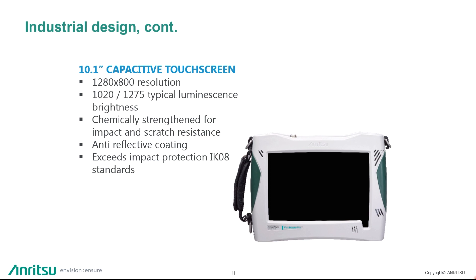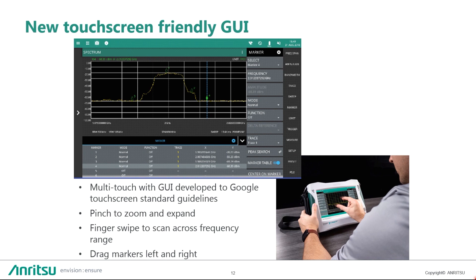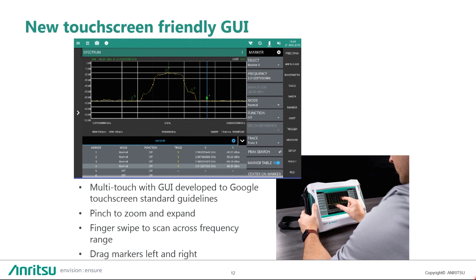We also created a new touchscreen with a friendly user interface. This is multi-touch GUI that is developed based on Google touchscreen standards, a set of standards by Google for apps that they recommend for things like size of a touch area, the way that certain icons functions interact with each other. We have functions like pinch to zoom and expand, finger swipe to scan across frequency range, and drag markers left and right. We also built this new platform on a Linux based operating system, so it's future proof and reliable.